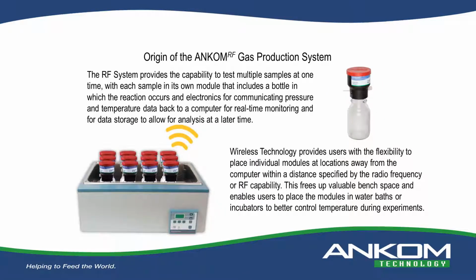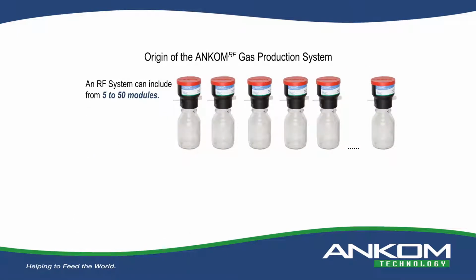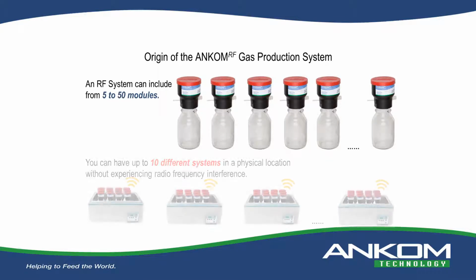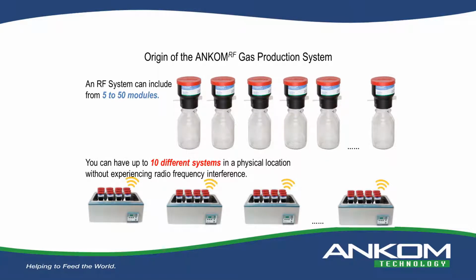Wireless technology provides users with the flexibility to place individual modules at locations away from the computer within a distance specified by the radio frequency, or RF, capability. This frees up valuable bench space and enables users to place the modules in water baths or incubators to better control temperature during experiments. An RF system can include from 5 to 50 modules, and you can have up to 10 different systems in a physical location without experiencing radio frequency interference.